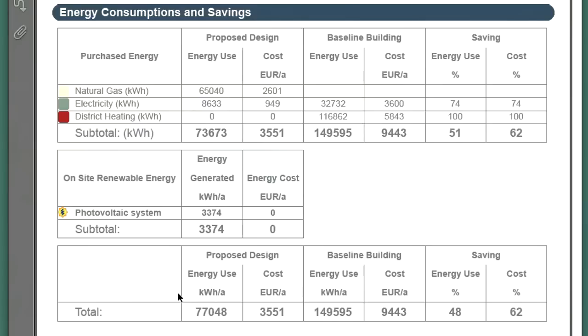Finally, let's display the Energy Consumptions and Savings Table. Electricity-related cost savings associated with the proposed building design are almost 75% compared to the mediocre solution represented by the baseline building. The designed building's overall energy use is 51% less and its energy costs are 60% less than the baseline building's.